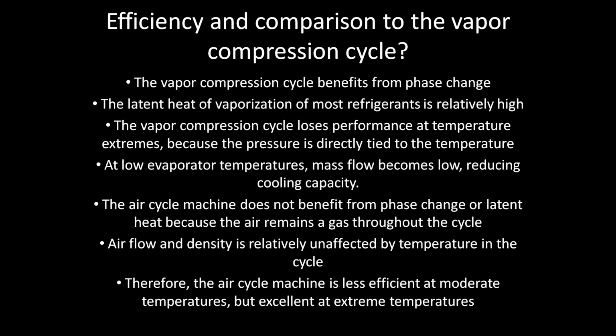The air cycle machine does not benefit from that latent heat of vaporization. It doesn't have a phase change. The air is a gas the whole time it's in a cycle. However, even though it doesn't move as much heat as the vapor compression cycle does, one thing that it has an advantage of is the amount of air flowing through the system is relatively unaffected by the temperature. And because of that, you can reach those extremely low temperatures that we were just talking about.